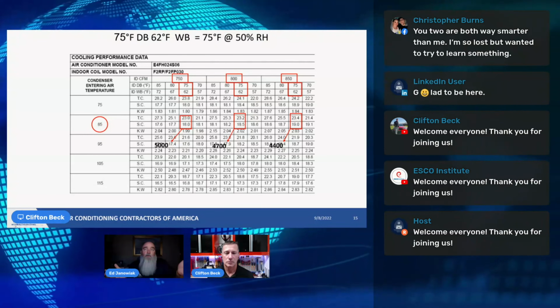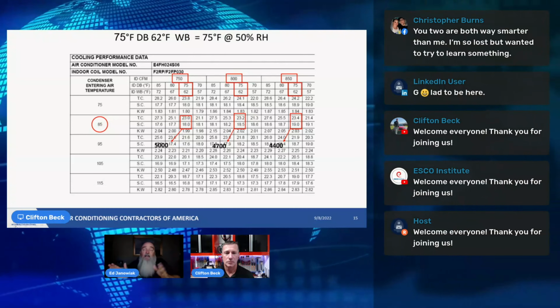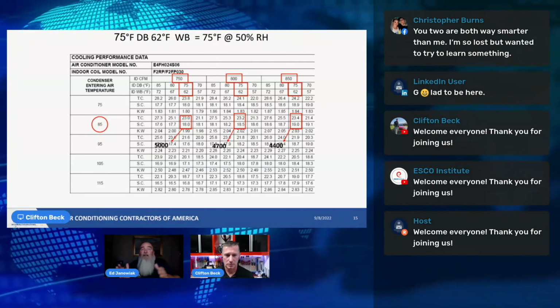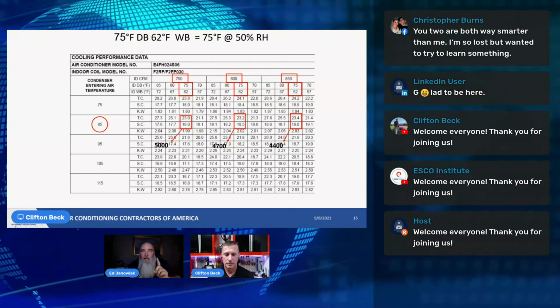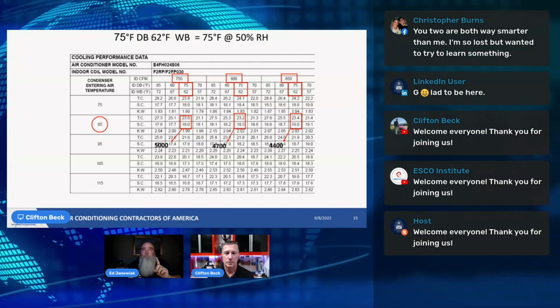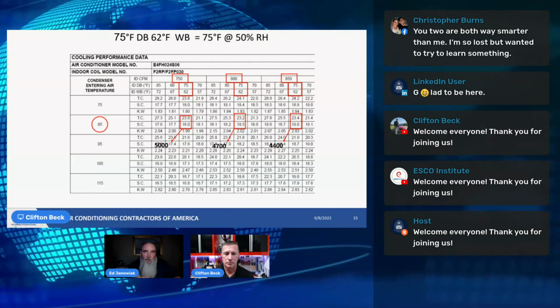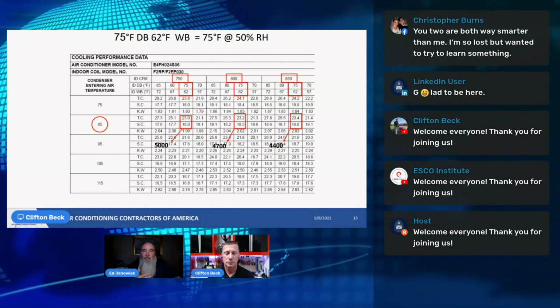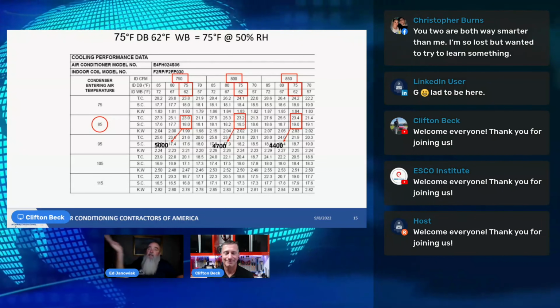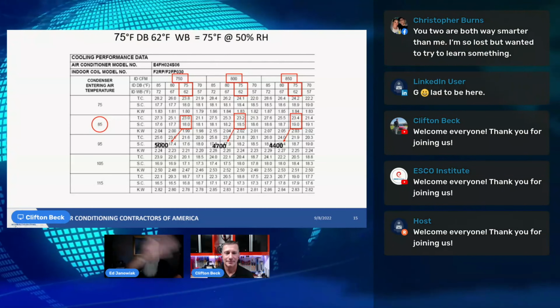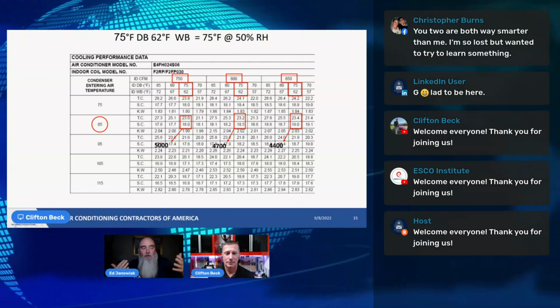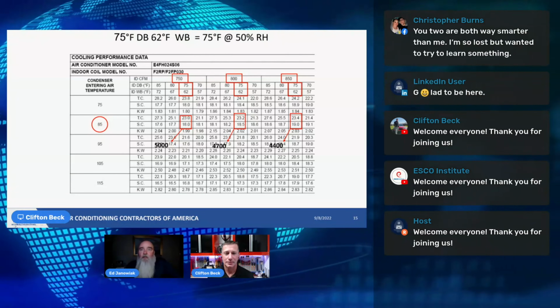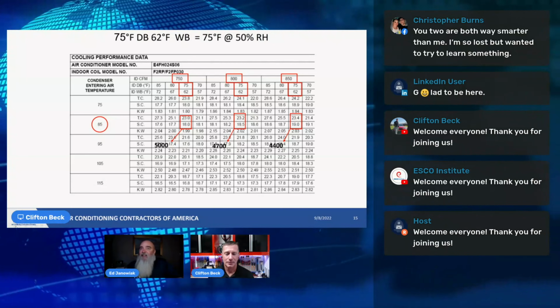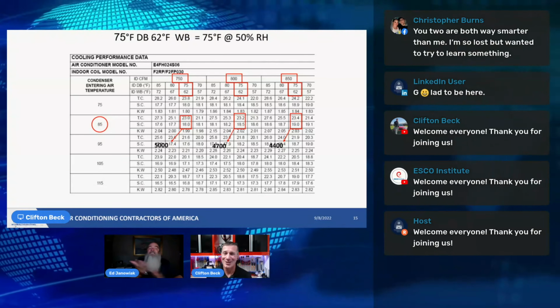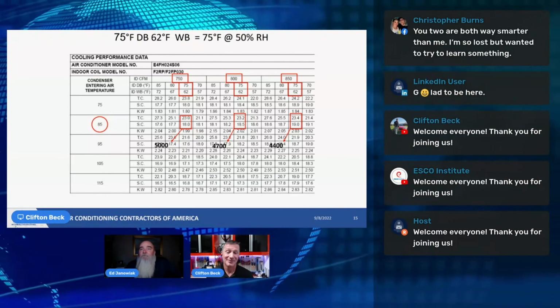See a trend as we move to the left, as we slow the air down, we're going to see a decrease in total capacity, a decrease in sensible capacity, and an increase in latent capacity. Just the way the slide before talked about sensible heat ratio, that's the math. That's showing you that I'm not full of soup. Right. Absolutely. And that's a good way to say that. Yeah, so no, it's a matter of plugging numbers.